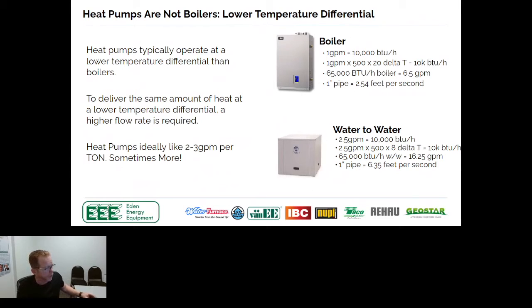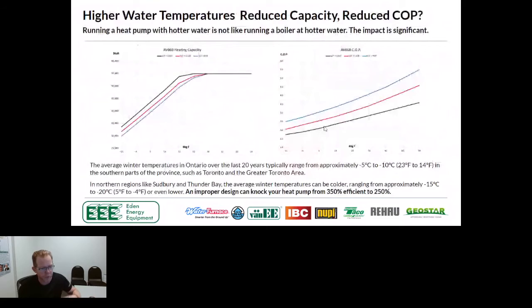Now, there's a bit of a distinction here. It's the whole conversation of running versus working, right? We want to make sure that we have really good flow because we want to make sure that we've got good performance out of that unit. So as we look at that unit, we want to make sure that we not only have good flow out of the unit, but that we've got the proper leaving load temperature. If I don't have enough flow through that heat pump, then what do you think my discharge water temperature is going to do?